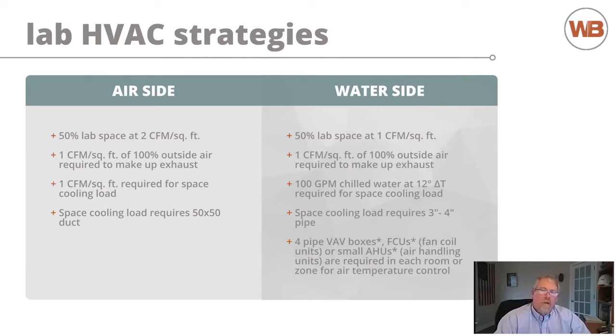The other side of this is the waterside comparison approach, and you have the same thing at the top, but instead of 2 CFM a square foot for the 50% lab, you'd have 1 CFM a square foot, provided strictly to make up the lab exhaust requirement. From there, you would provide the other half, which would have been 1 CFM a square foot, for sensible cooling. You look at it from a chilled water standpoint, and there are DX refrigerant strategies that could be even smaller, but let's just stay on the waterside discussion for a second.